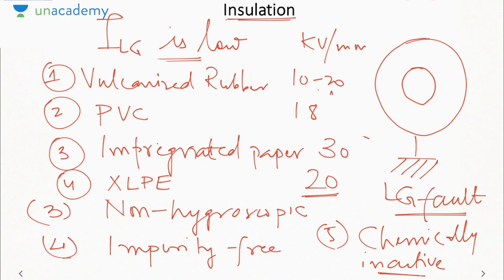Now based on whatever is the electric field that is being generated inside the cable, because dielectric strength should always be greater than the maximum value of electric field, based on that we will choose the insulation. So first you will have to estimate the maximum electric field inside the cable.